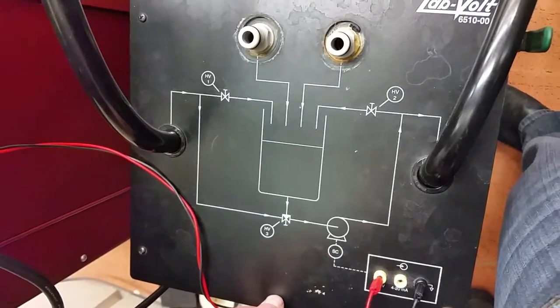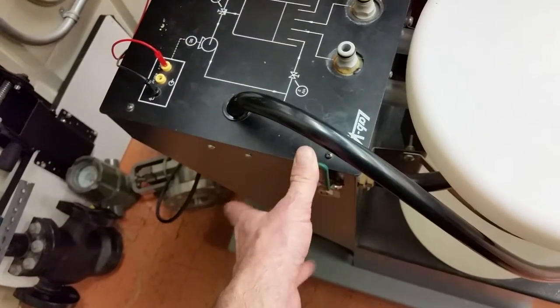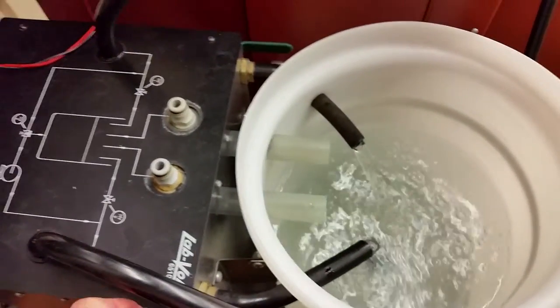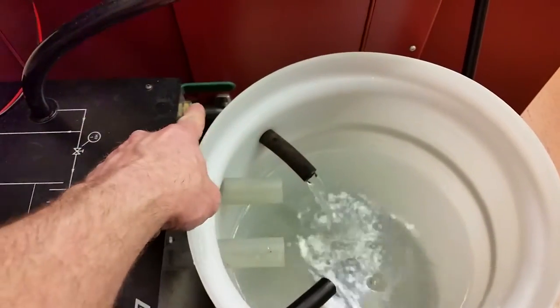Valving: HV2 is closed — that's the bypass valve. If I open it, a portion of my flow comes back to the tank, which I don't want; I want all the flow going to the field. My return is on HV1, so I need it open. HV3 is pointing up, meaning all of the water from the tank is going to the pump.